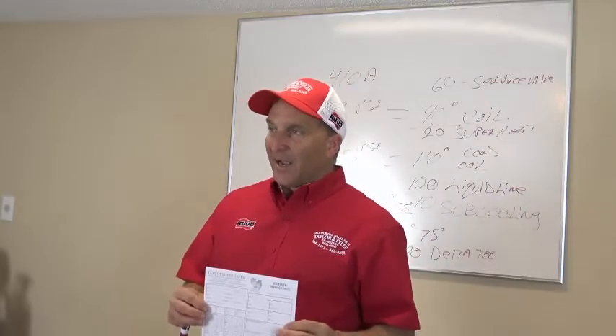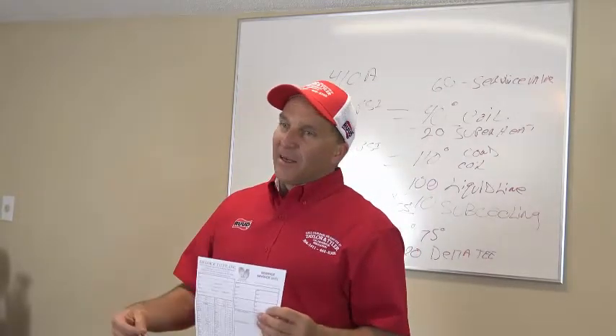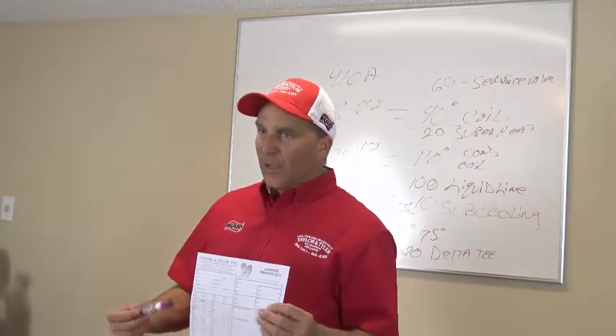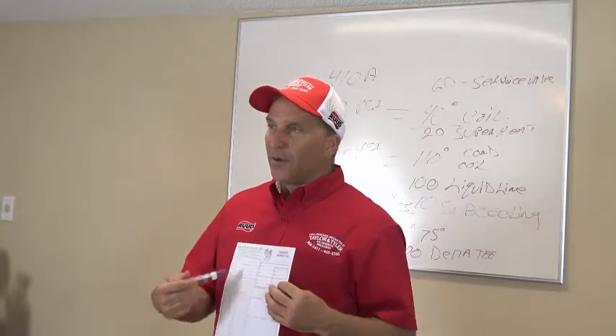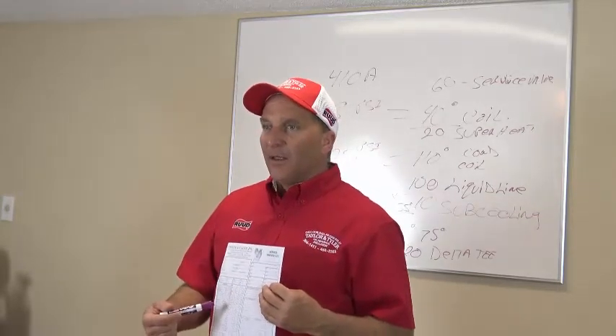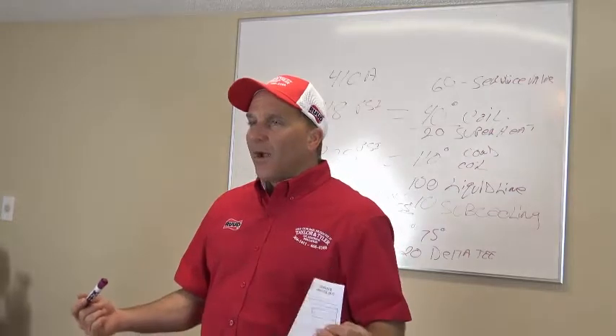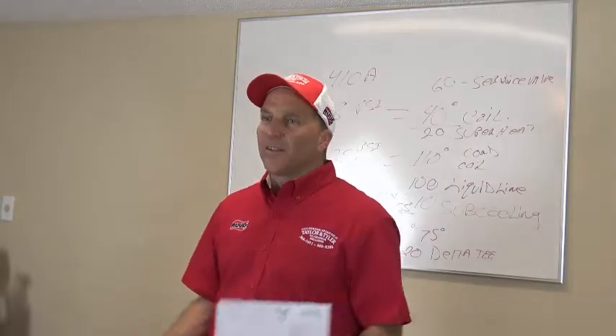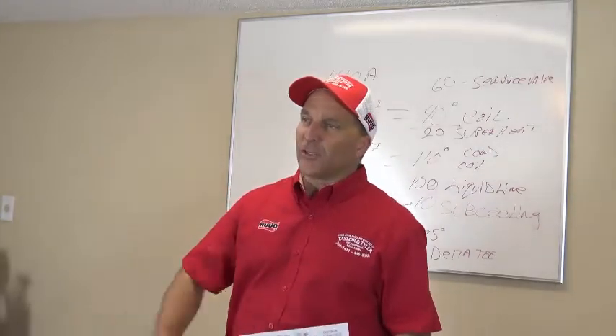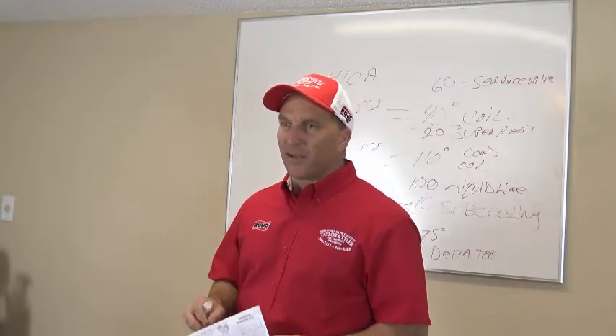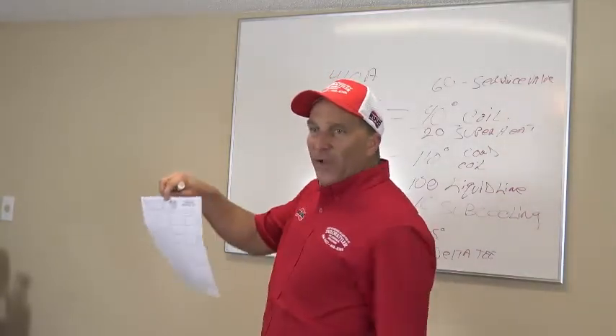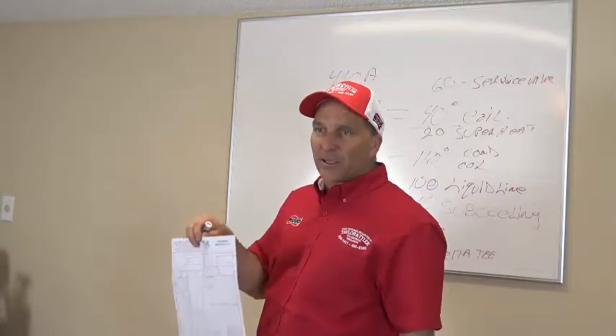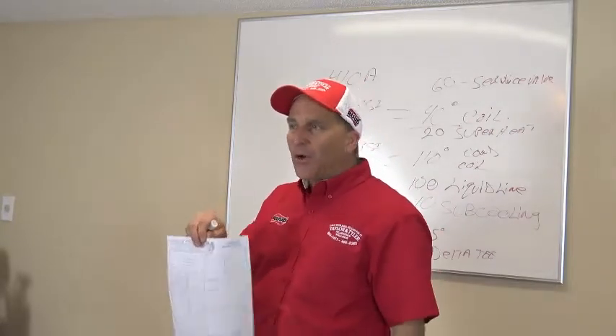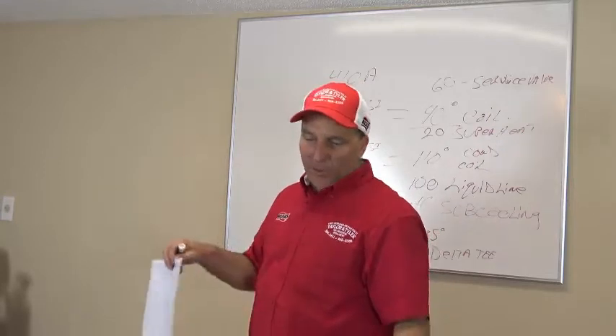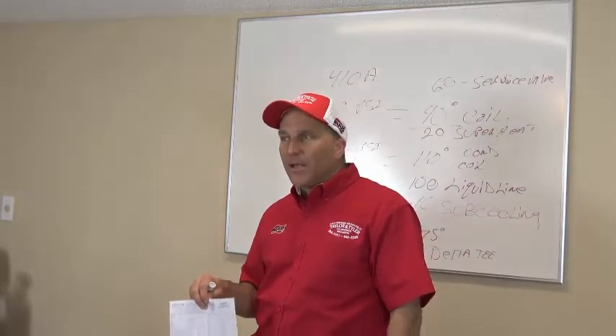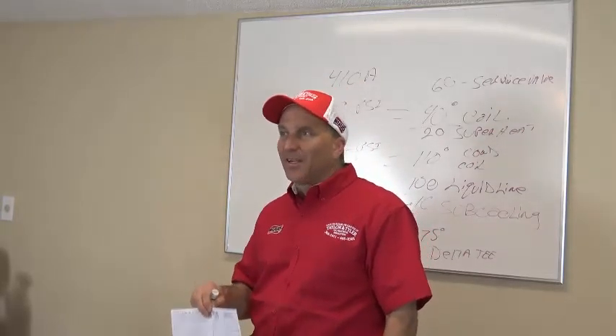The last technician I had last year, every single customer he would go to, he would just put, okay. And I'd say, Sean, why are you not cleaning these condensers? They're not dirty. So I started pulling history up on all these systems. And I'm like, look, we haven't been there in 4 years. Look, we haven't been there in 3 years. Look, we haven't been there in 2 years. How can you tell me the condenser is not dirty? Well, it don't look dirty. Clean it. Clean it. I'm telling you, clean it.